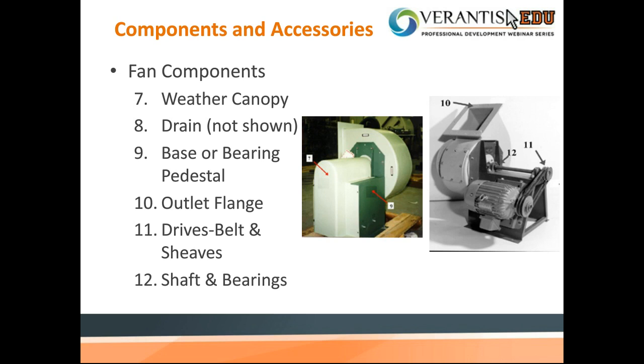Craig, can I interrupt one second? Sure. With the drains on a fan, they need to be properly trapped. If they're not properly trapped, you can end up with water buildup inside the housing, which is eventually going to start causing some erosion as it's beat around inside the fan.